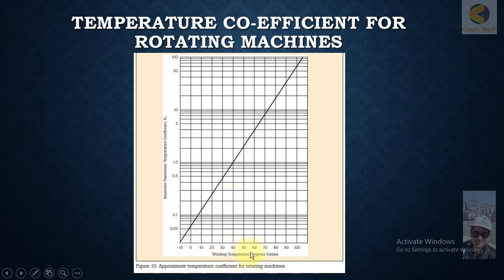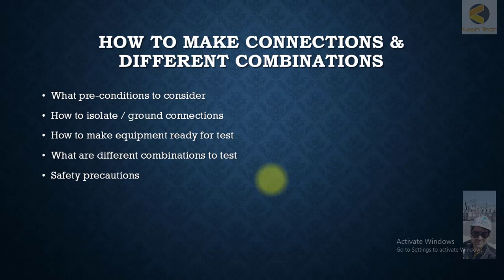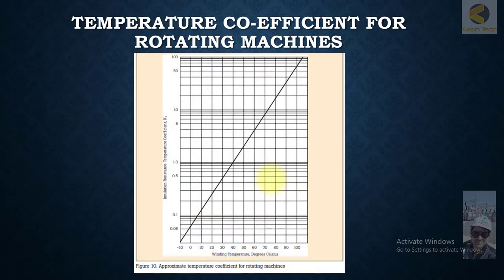Here you can see the winding temperature and there's a curve. If temperature is increasing from minus 10, for example, then this insulation resistance temperature coefficient is also increasing. You can get these curves from the manufacturer of specific items and then calculate equivalent temperature. Thank you very much for this small topic.